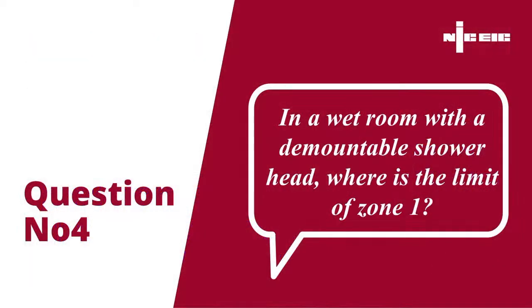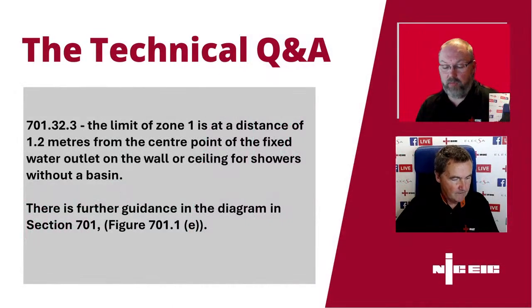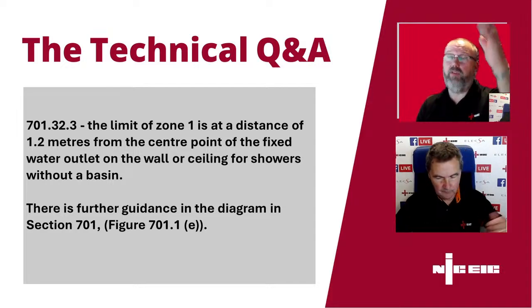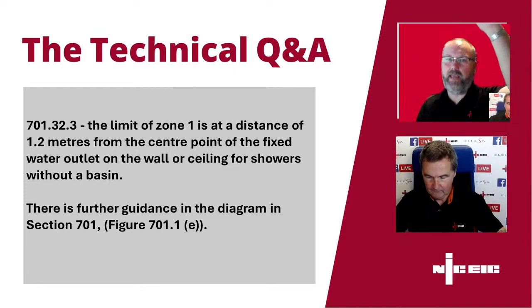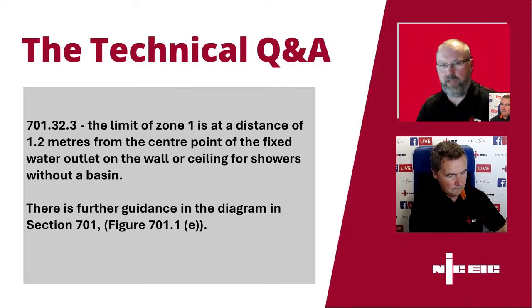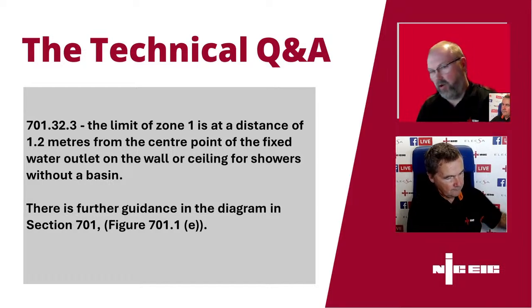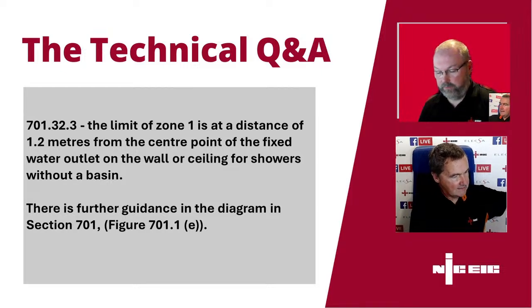Okay, another one that often comes into the helpline. In a wet room with a demountable shower head, what's the limit of zone 1? What's our thoughts there, Craig? The limit on zone 1 is 1.2 metres from the fixed water outlet. So that is generally the fixed. If you've got a fixed head on the wall or a fixed head overhead, it's from that point onwards, and we don't need to extend it even if it's demountable. That's the point that we're looking at. So 1.2 in an arc from that position. Yeah, and it's nice and clear.